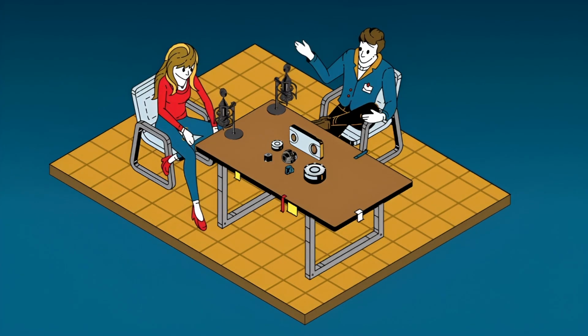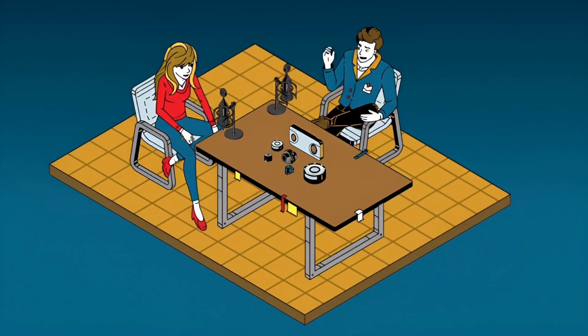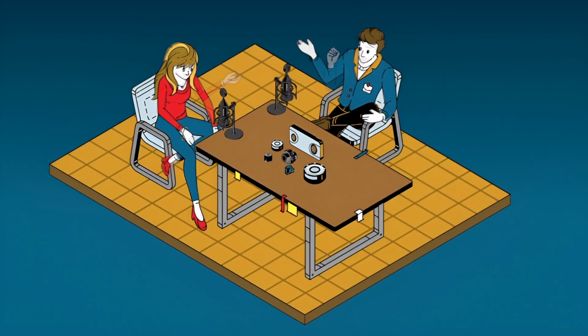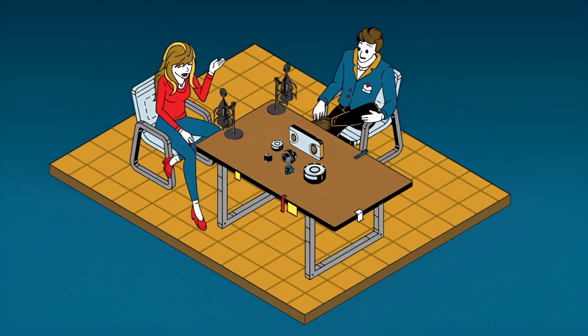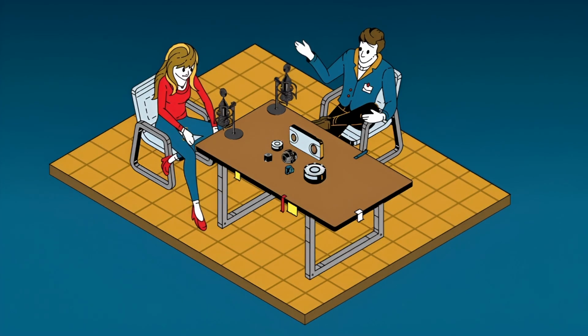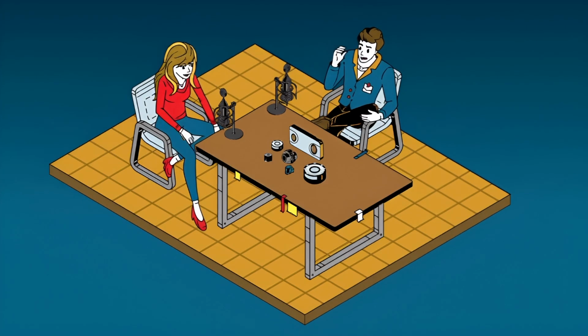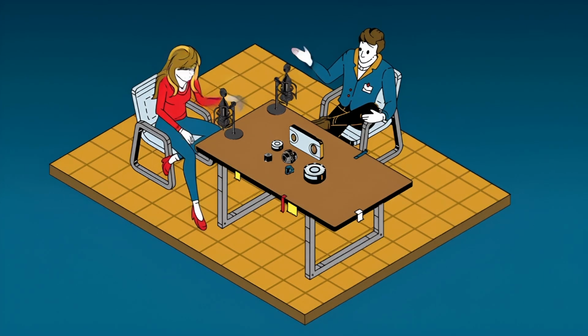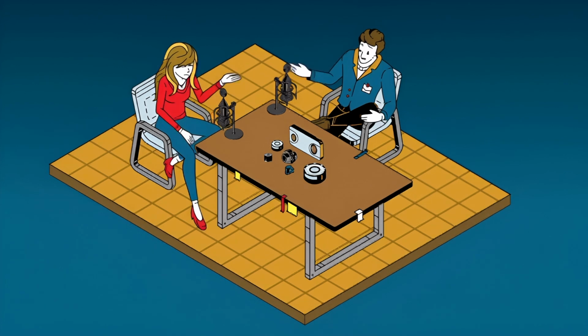If an engineer only tests a prosthetic leg using a single-axis load cell, meaning they just press straight down on it repeatedly in a lab, they are entirely blind to the reality of how that device will actually be used. It would be like trying to describe a 3D movie while only looking at a 2D photograph. Exactly. You miss all the depth. This is why multi-axis sensing is absolutely mandatory for advanced biomechanical engineering. Because if you only measure the vertical axis, you have absolutely no idea what the shear forces, the side-to-side forces, are doing to the socket, where the prosthetic actually attaches to the patient's residual limb. Right. And that lateral friction is exactly what causes tissue damage, blistering, or eventual microfractures in the structural joints of the prosthetic itself. So the multi-axis sensor fixes that blind spot.